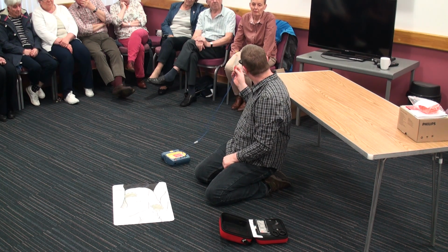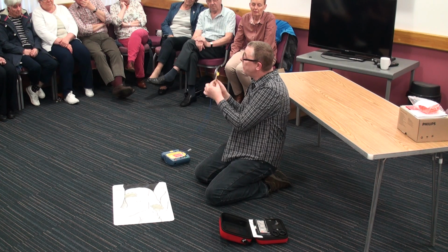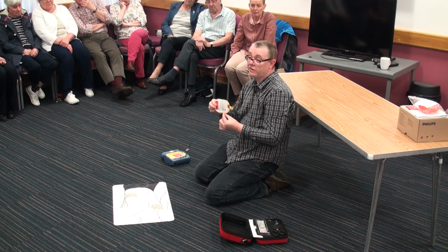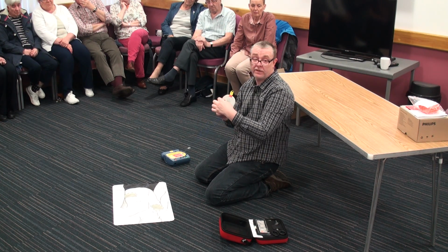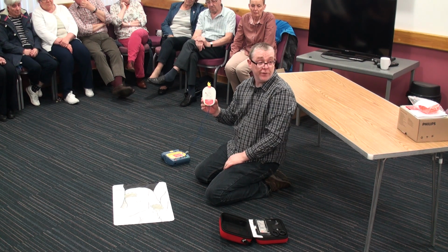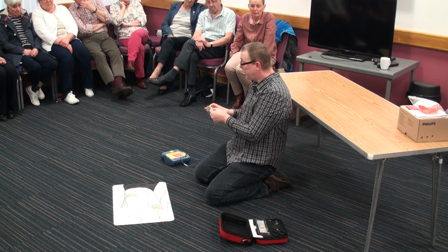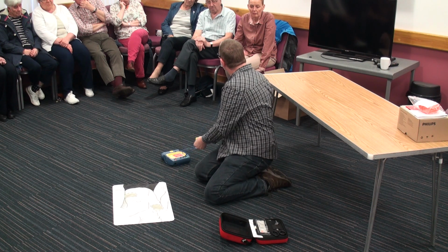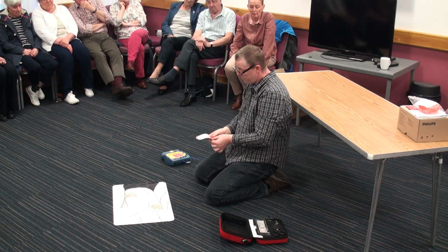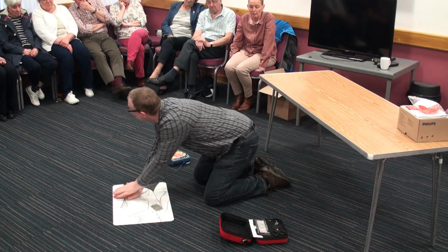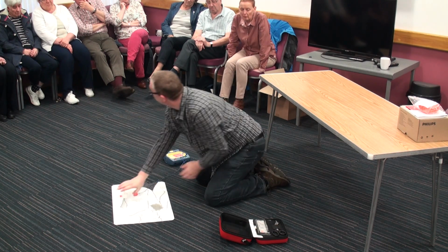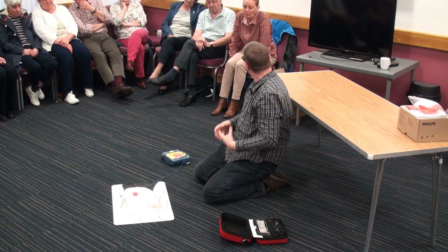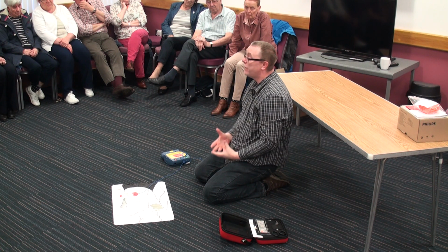On each pad, there's a picture of approximately where the pad should be placed on somebody's chest. The machine will only do one thing at a time. Place pad exactly as shown in the picture. Press firmly to patient's bare skin. Okay? It's going at a really slow pace here, as if I've never used the device before.